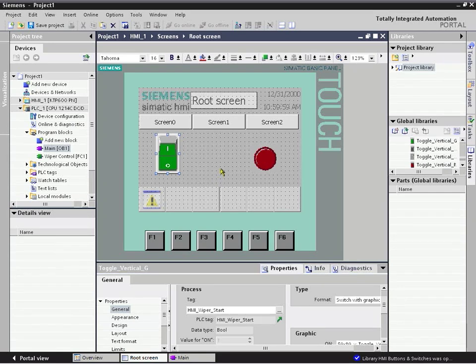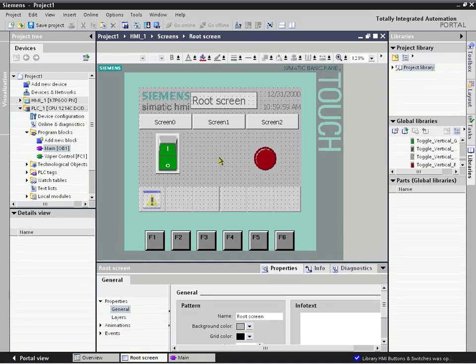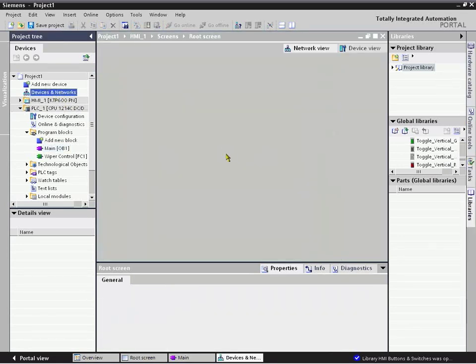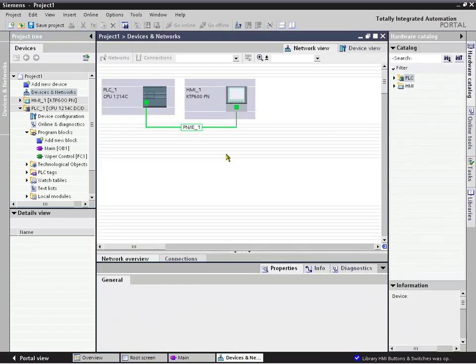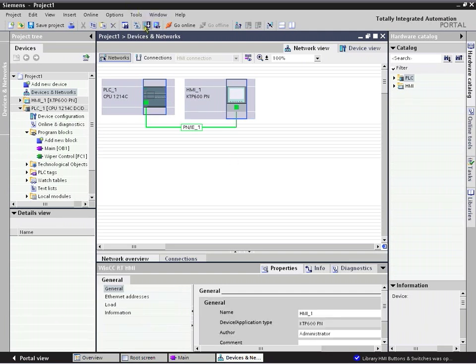So now we've made changes by adding a device to our project, the HMI device, and then we also updated our PLC logic. To download those, we can do these simultaneously because in Step 7 Basic for the S7-1200, it not only includes logic control and HMI control but networking too. So we can highlight our two devices and our graphical connection in this network view and decide to download changes that we made to both of them simultaneously.